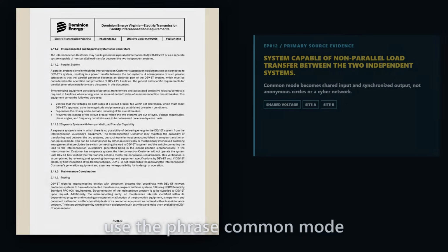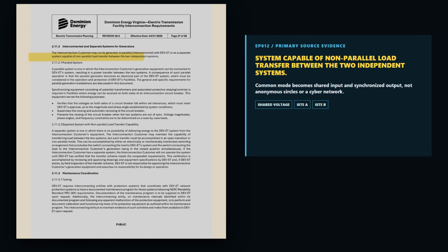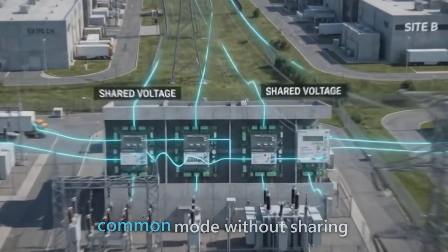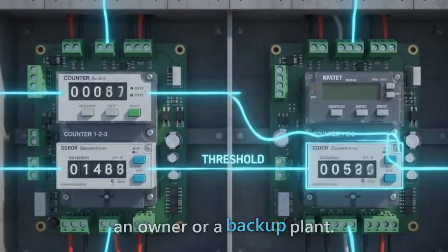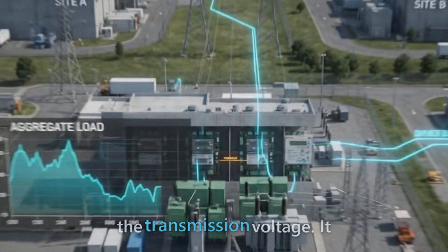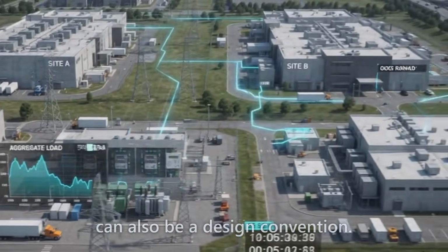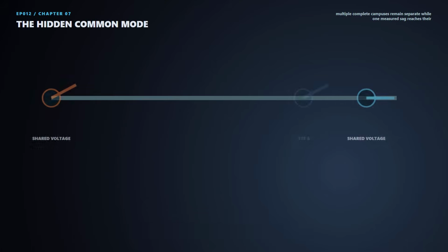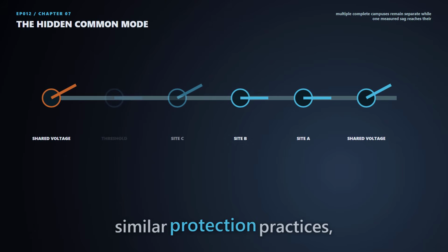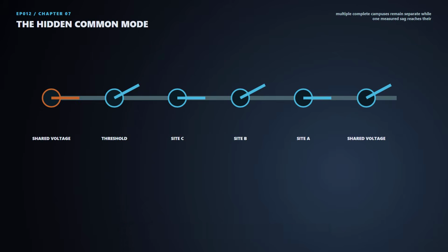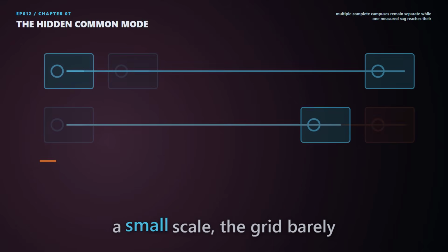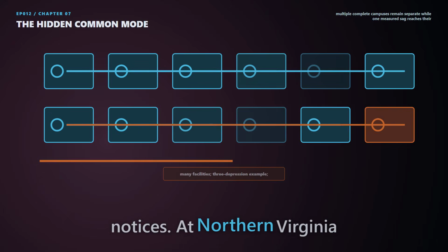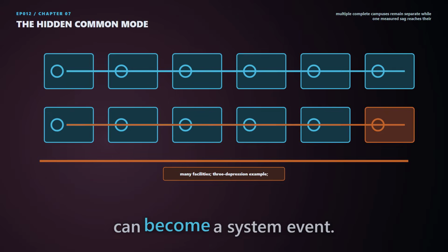Engineers use the phrase common mode when systems that appear independent share a vulnerability or trigger. Dense data center regions can create a common mode without sharing an owner or a backup plant. The shared element can be the transmission voltage. It can also be a design convention. Facilities buy similar UPS equipment, follow similar protection practices, and optimize for the same goal. Never let unstable utility power reach the computing load. At a small scale, the grid barely notices. At Northern Virginia scale, identical caution can become a system event.